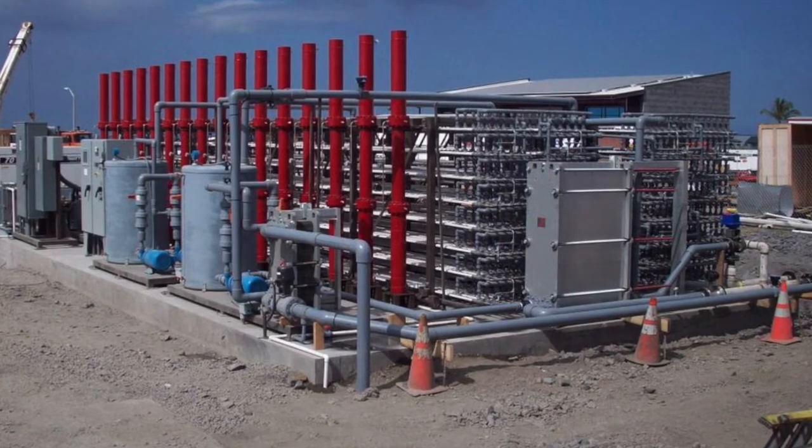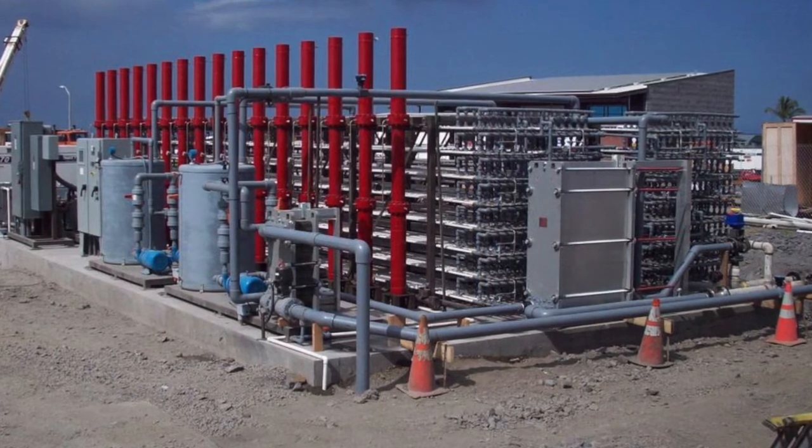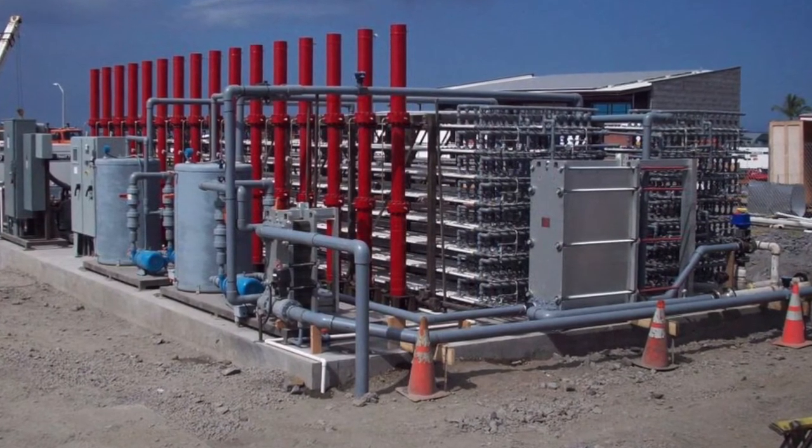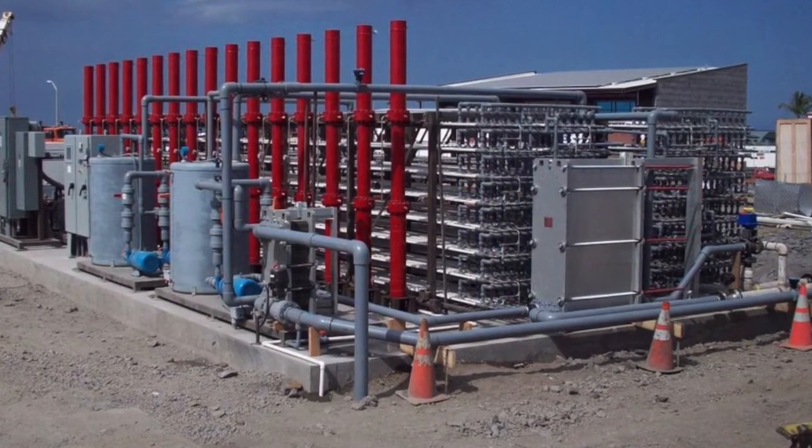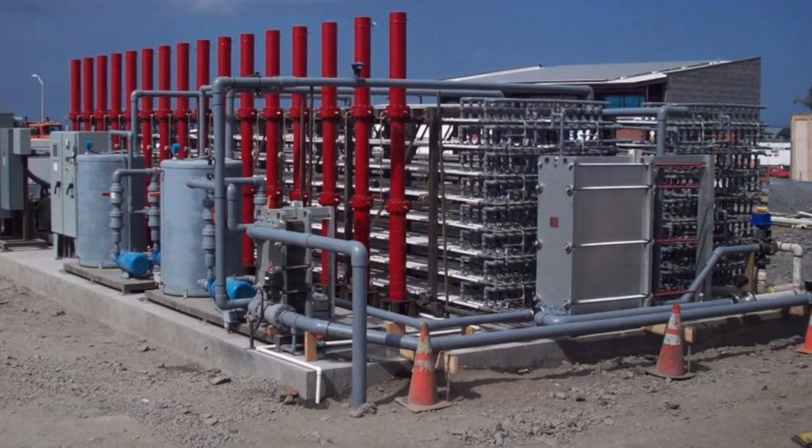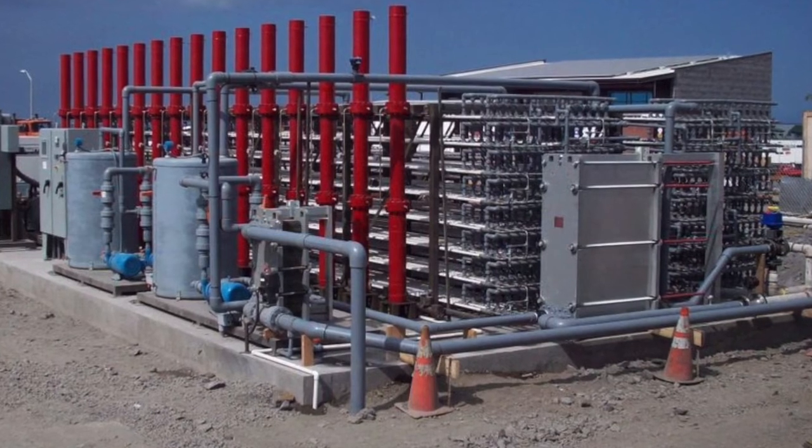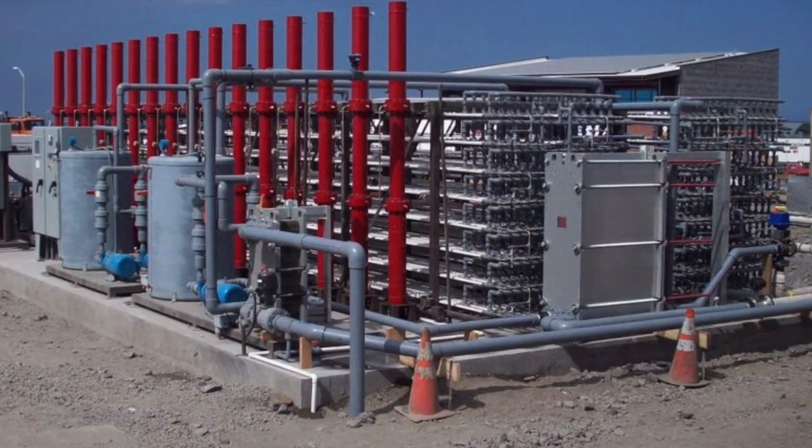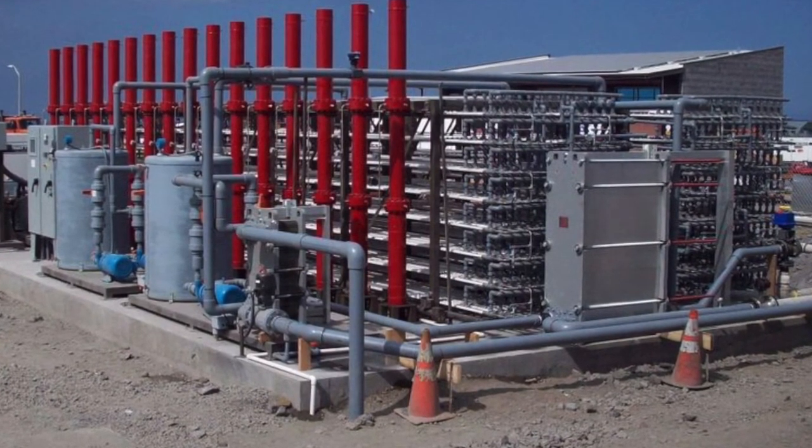Full-scale power plant modules contain approximately 32 cylinders. Their number is determined by the resource temperature, well flow rate, and horsepower desired. This cylinder redundancy also provides an option to bypass cylinders for maintenance, allowing the machine to continue making power 24-7.